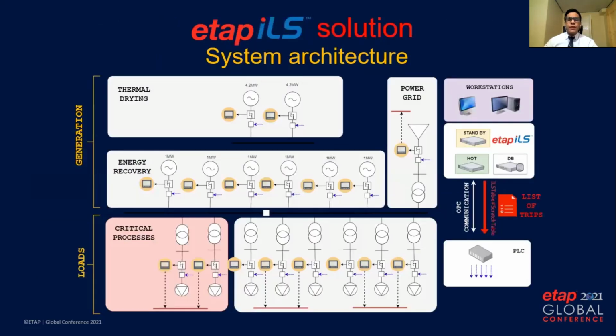For the implementation of the system, all the information of the protection relays, variable speed drives, soft starters, power factor controllers, power quality meters, circuit breakers, uninterruptible power units, automatic transfers, and other devices was integrated into the ETAP RT system via a Schneider OPC server. The data is stored in a historical database which is consulted in real time by 2 workstations, which have human-machine interfaces, HMIs, which facilitate the interpretation of the data in the one-line diagram or through personalized graphics.